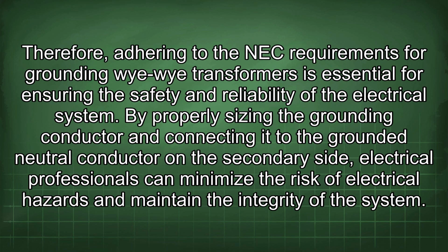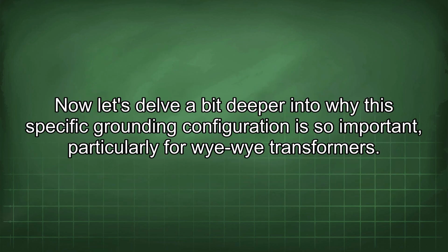Therefore, adhering to the NEC requirements for grounding Wye-Wye transformers is essential for ensuring the safety and reliability of the electrical system. By properly sizing the grounding conductor and connecting it to the grounded neutral conductor on the secondary side, electrical professionals can minimize the risk of electrical hazards and maintain the integrity of the system. Now let's delve a bit deeper into why this specific grounding configuration is so important, particularly for Wye-Wye transformers.